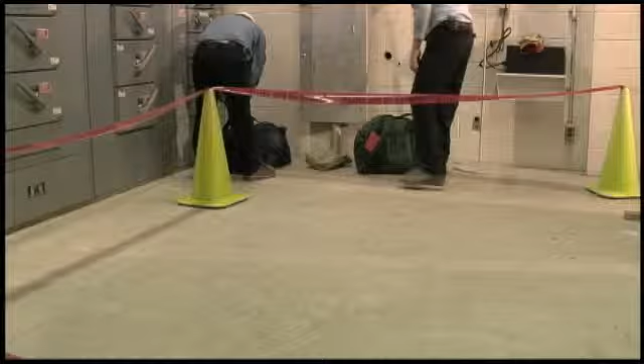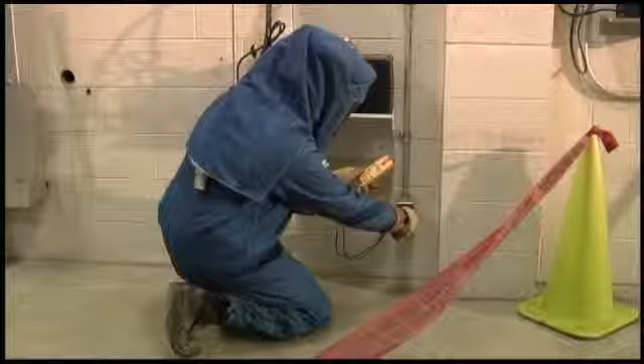If you are not authorized, do not approach equipment when the arc flash hazard boundary is active. The boundary extends in all directions from the energy source, like a 3-dimensional bubble. It is only active when someone is performing a task with or on the electrical equipment. To work within the boundary, you must be trained, authorized, and dressed in the required personal protective equipment.